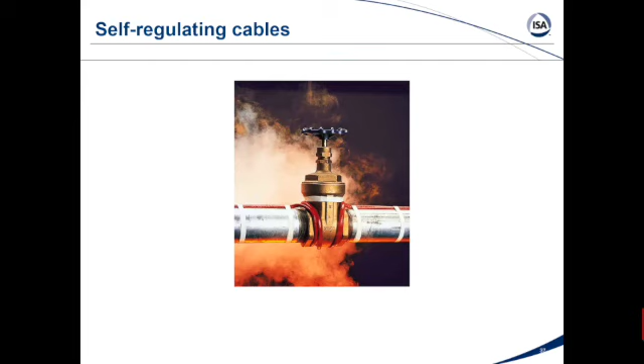So self-regulating cables, I'll get into that technology a little bit because that is most common today. I'll talk quickly about self-regulating and our mineral insulated cable. So self-regulating technology is the magic, we'll say, in this cable, in this industry with heating cables. Hopefully, can you guys see the mouse pointer here? Is that visible to you? Okay, thank you. So when you look at these cables, you'll see numerous layers: outer jacket, braid, insulating jacket, and you have your heating core and your two elements. I'll explain a little bit about what's going on.